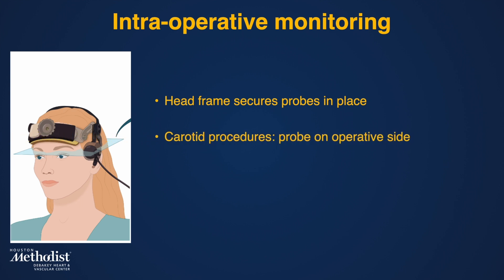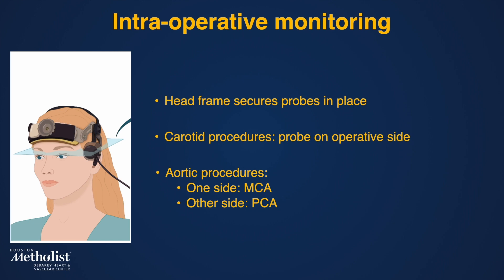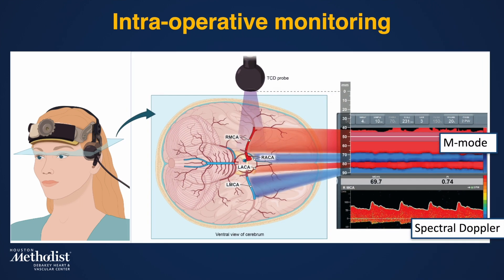The head frame ensures that the ultrasound probes used to insonate the cerebral arteries remain in place throughout the intervention. Because of the positioning of the head during carotid procedures, in most cases we only monitor on the operative side. Aortic procedures do not require a head turn in most cases; therefore, we often monitor the MCA on one side and the PCA on the other side. The TCD monitor will continue to display the M-Mode and the spectral Doppler signal.